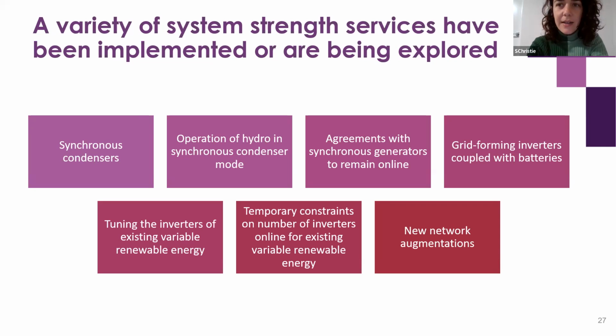I've listed on the slide the variety of services that we understand may be able to partially or completely meet the system strength requirements as we see the shift away from traditional providers of system strength. So we've got synchronous condensers, which James has explained in detail, fitted with flywheels to also get the inertia that helps for a separate system security issue. That's one of our options, synchronous condensers, and as Chris mentioned, it's a known technology and something we're comfortable with broadly.